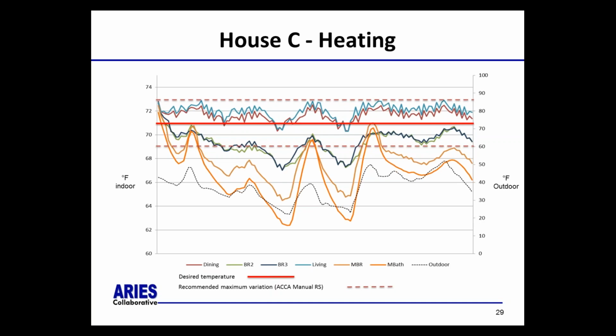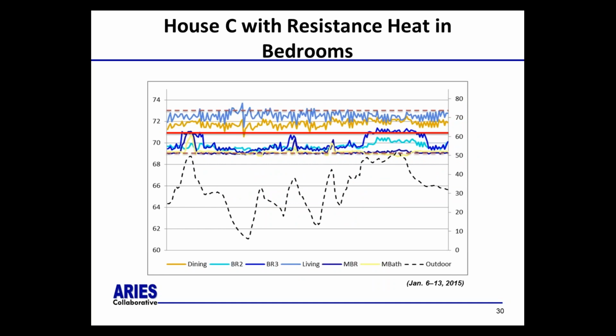House C, of course, with our transfer fans, had significant underheating down to the 60s in a couple of rooms, particularly that master bathroom and the master bedroom, which are the more difficult in this particular floor plan to communicate with the living room. So we found that we needed to add some resistance heat in those bedrooms, and we did that, and that maintained our temperatures. Of course, it added an additional energy consumption factor, which we have to account for, and which you'll see shortly. But this is another cold period where we tested with the resistance heat and maintained the temperatures in those bedrooms.